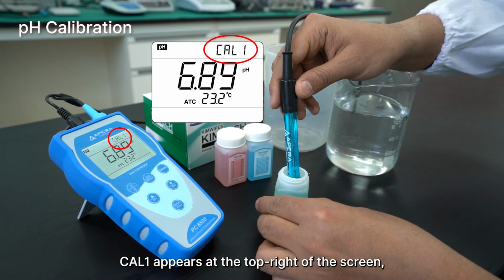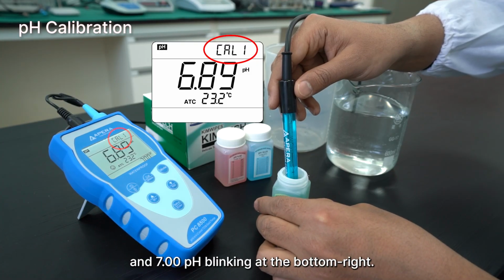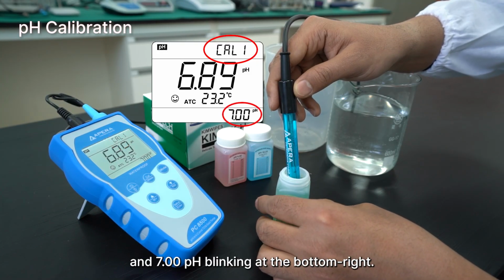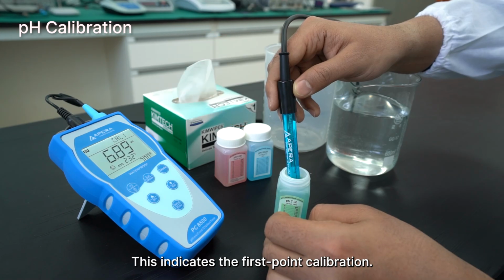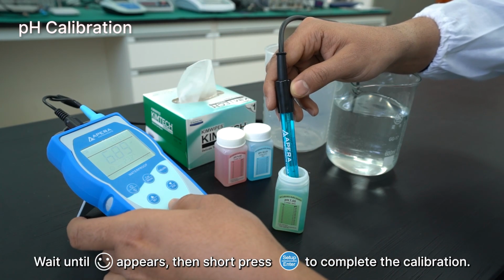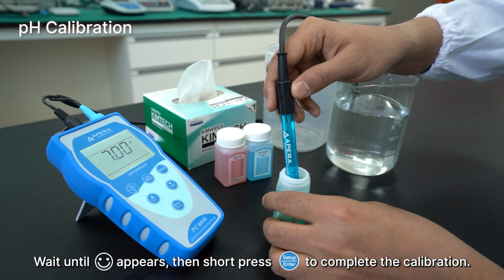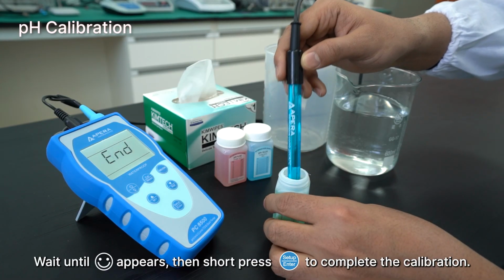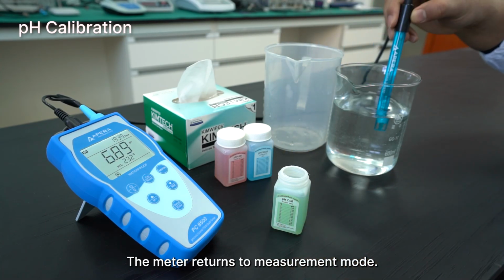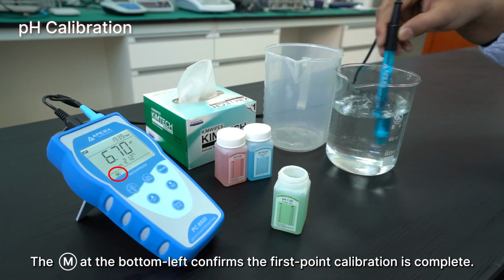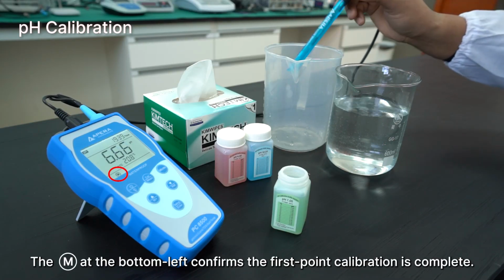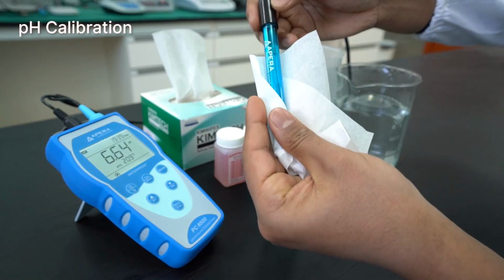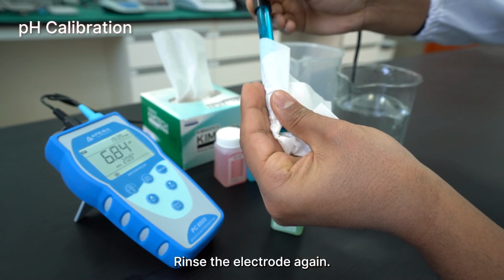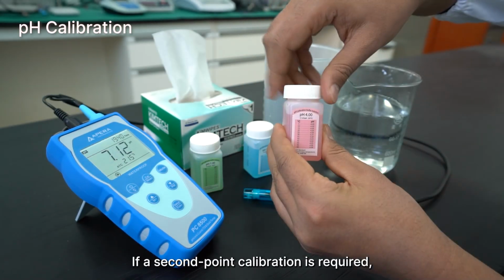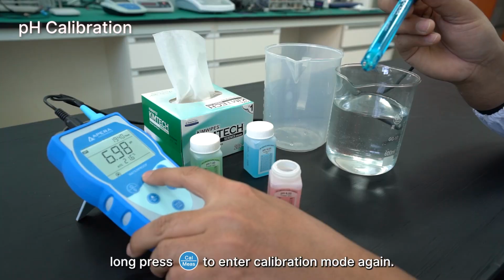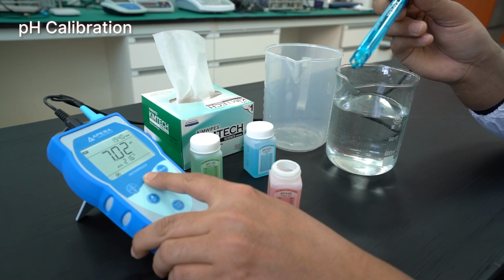Cal 1 appears at the top right of the screen and 7.00 pH blinking at the bottom right. This indicates the first point calibration. Wait until the smile icon appears, then short press Enter to complete the calibration. The meter returns to measurement mode. The M icon at the bottom left confirms the first point calibration is complete. Rinse the electrode again. If a second point calibration is required, long press Cal to enter calibration mode again.